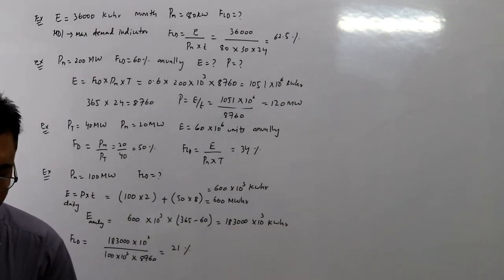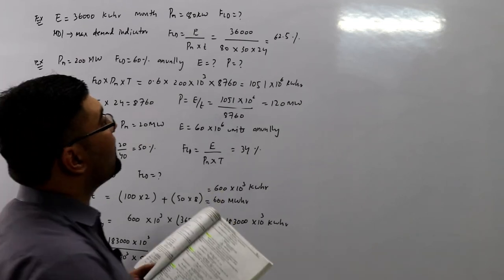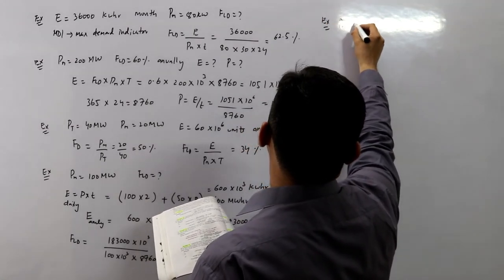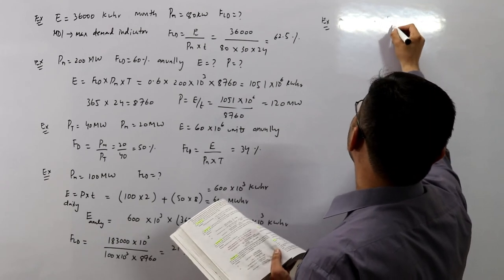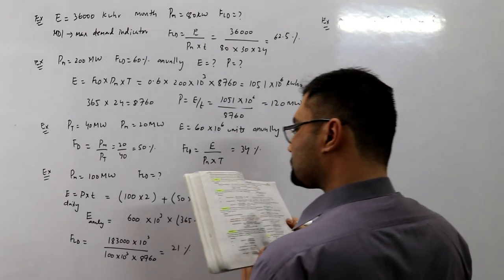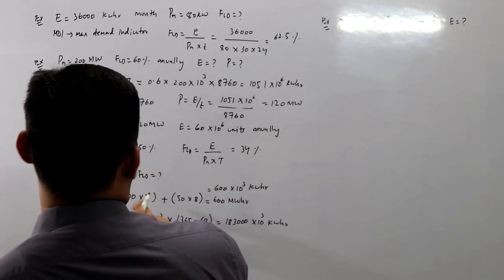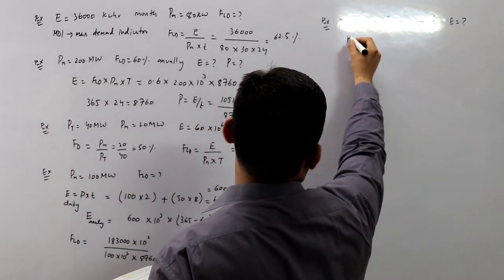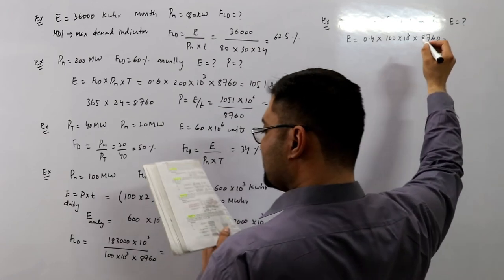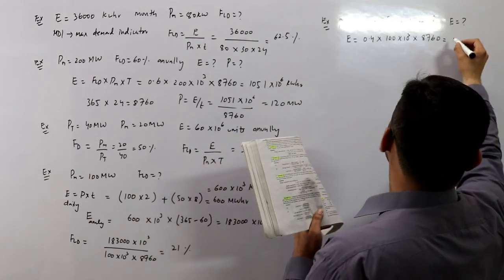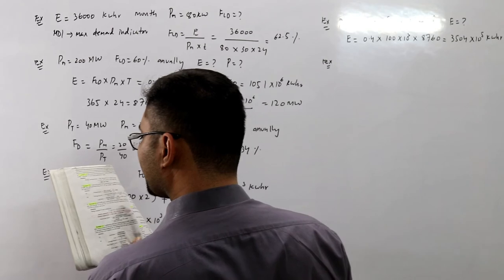From the book: a power station has a maximum demand of 100 megawatts and annual load factor of 40 percent. Calculate the total energy generated in the year. e = fld × pm × t = 0.4 × 100 × 10³ × 8760 = 3504 × 10⁵ kilowatt hours.